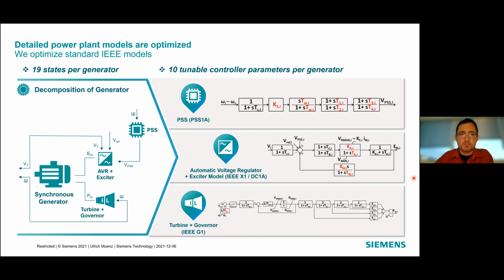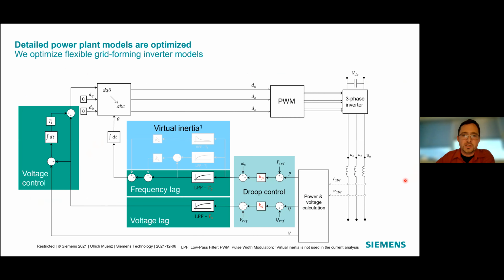Now, this is a conventional plant; let's look at a grid forming inverter. This is the model for a grid forming inverter that we use in our system. It's a fairly standard control structure, with droops and low pass filters for both frequency and voltage, and a fairly simple voltage controller. We also have a component for virtual inertia, which we are not using at this point, but we plan to use later to see if it has advantages. Here we are tuning the time constants and the droop gains.